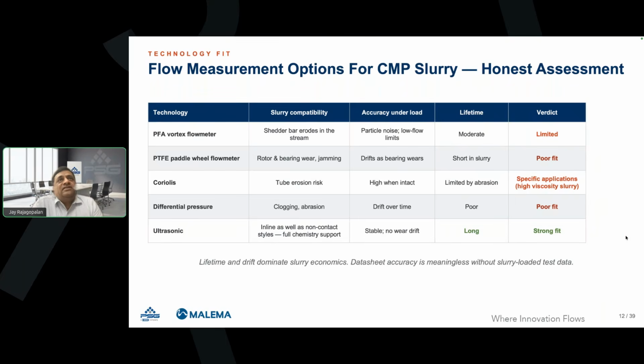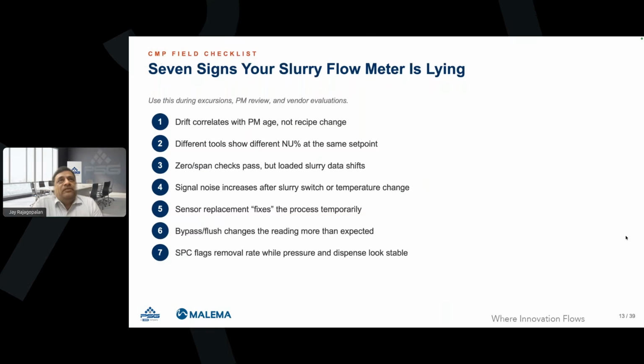There are 7 signs that one should look into to tell whether the slurry flow meter or flow controller is lying. This is critical, so I'm giving it in a handout. Too many details, but I'll highlight some of them. For example, signal noise increases after a slurry switch or temperature changes. That's a sign which can lead to flow meter issues. And drift, whether it is drifting over a period of time and not because of a recipe change, could be one of the flags.